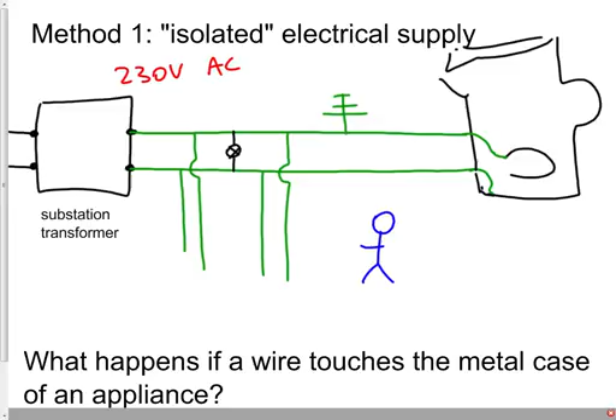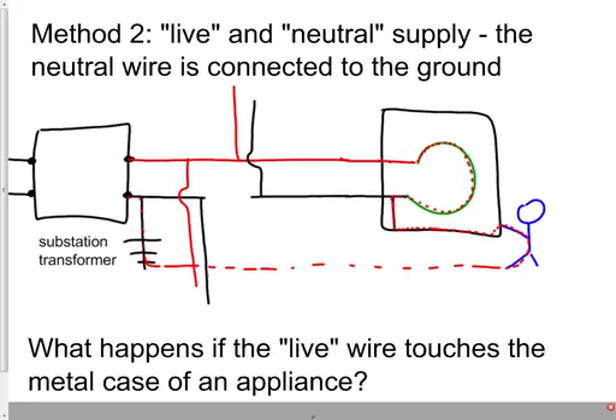So the reality is complicated, and there are lots of different systems in use in different countries. However, the general principles I've explained should be right: isolated supplies are inherently very safe but unpredictable if deployed over large scale applications where something could go wrong. Defining the neutral wire by grounding it somewhere makes the live and neutral very predictable in their behaviour, and having an earth wire separate from the live and neutral means your appliances are still safe if the neutral wire somewhere gets cut — it doesn't make your metal cased appliances all live.